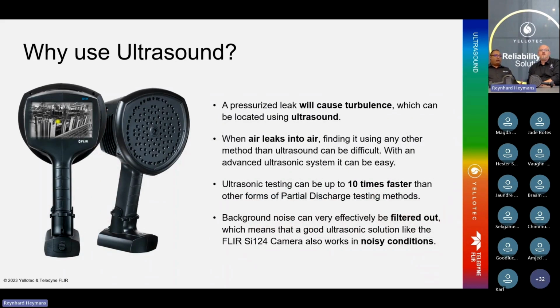So why ultrasound? A pressurized leak will normally create a lot of turbulence. And unfortunately, the only technology that's able to see this is ultrasound. When air leaks into air, it's very difficult to detect other than using ultrasound. Also, when it comes to partial discharge, you can scan a substation 10 times faster than with any other technology available. You're able to filter out any background noise. And again, seeing is believing, it's more visual.